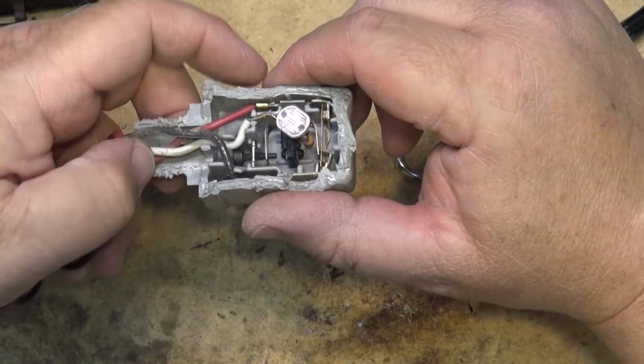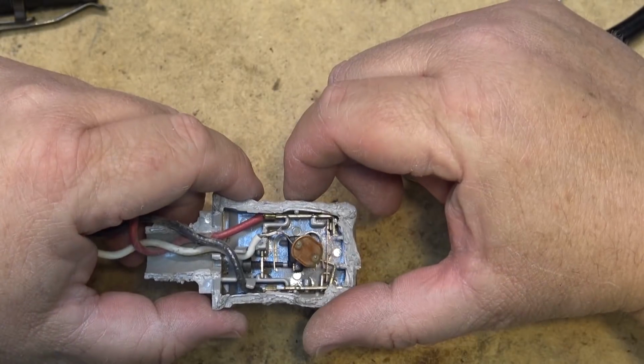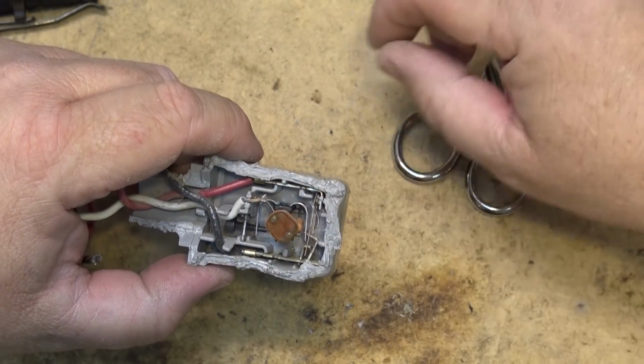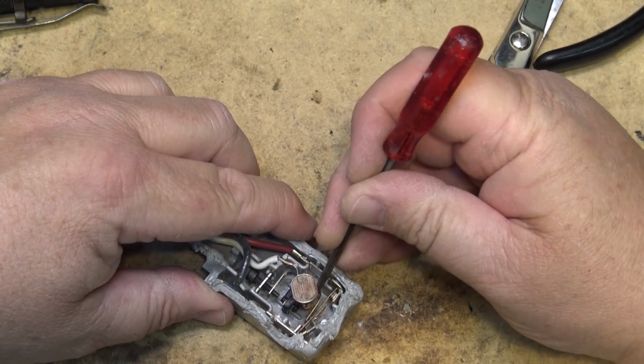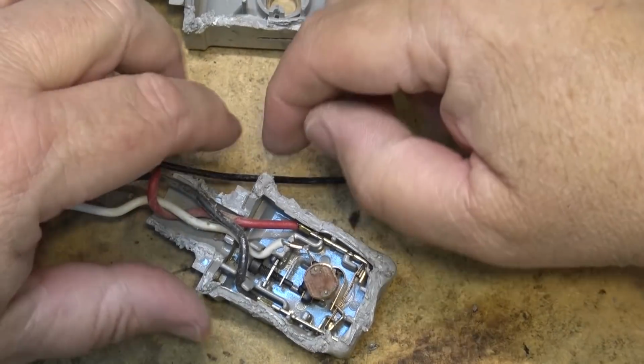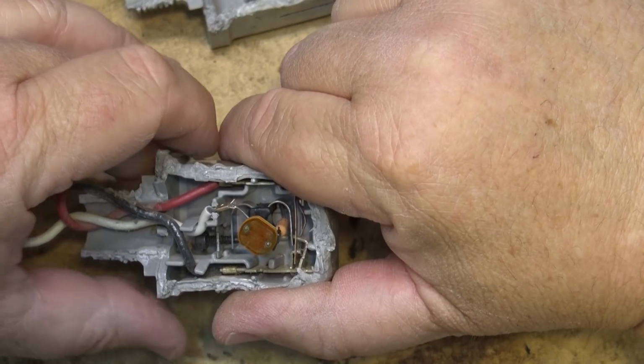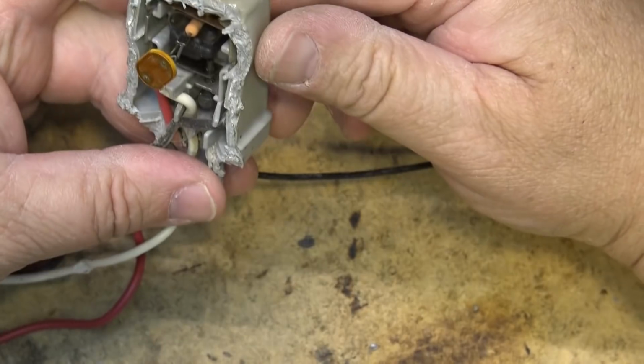And what happens is when light passes through the photocell, it heats this resistor up. And when the resistor heats up, the bimetallic strip here will flex. So as we can see, one of the reasons why this case is so thick is it wants to preserve the heat.